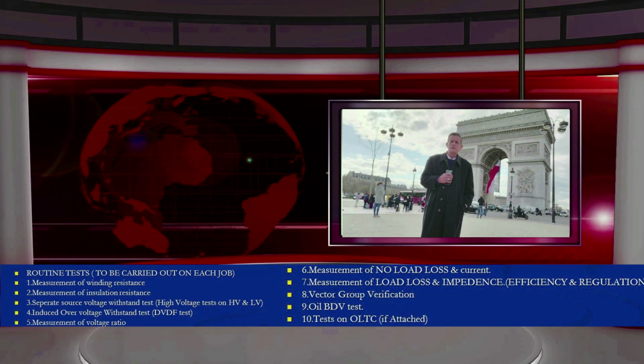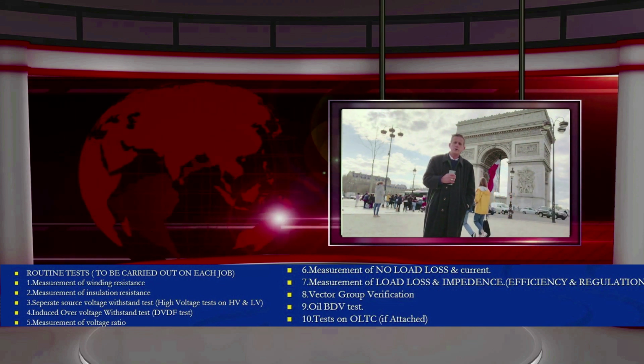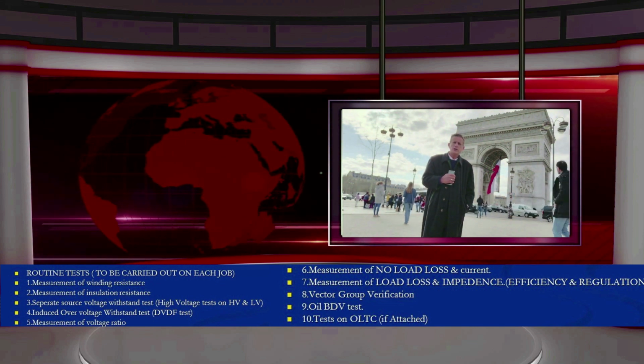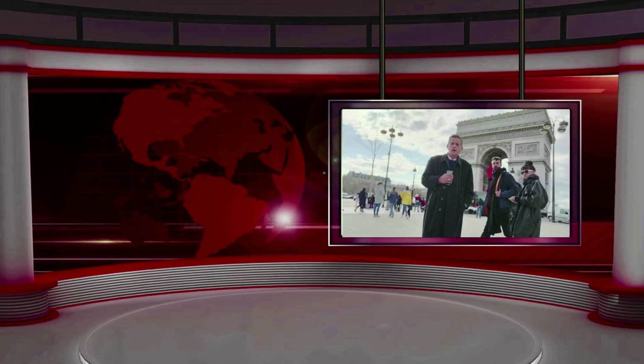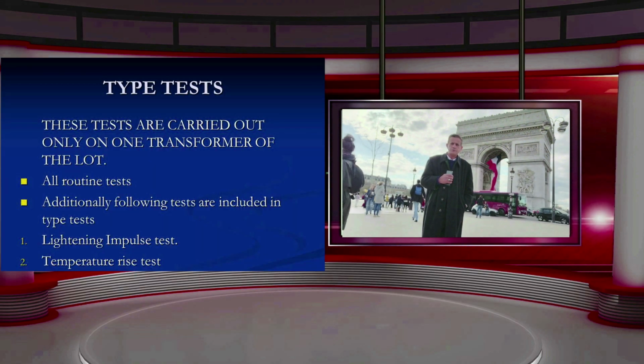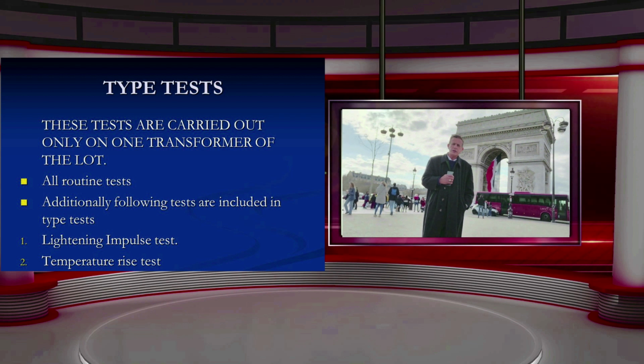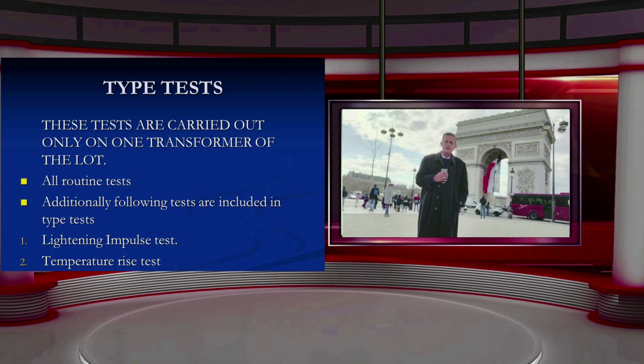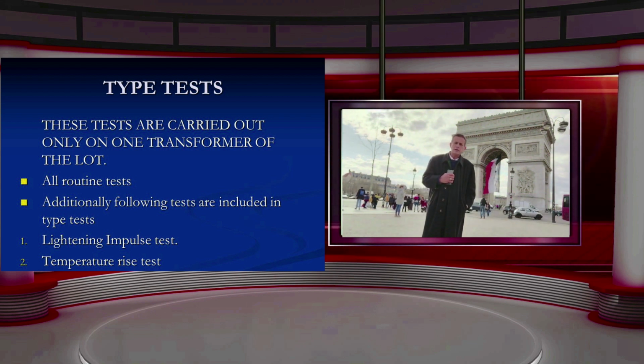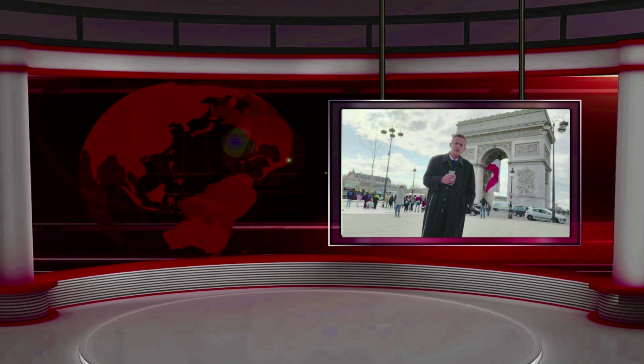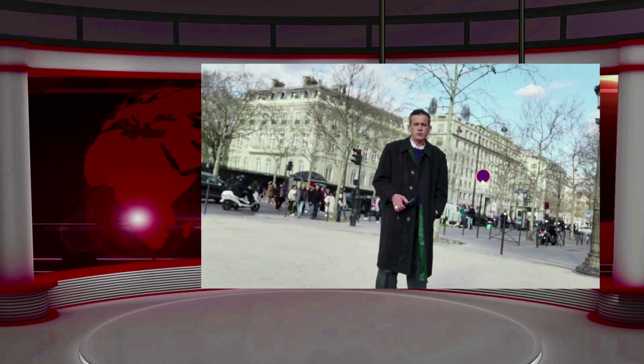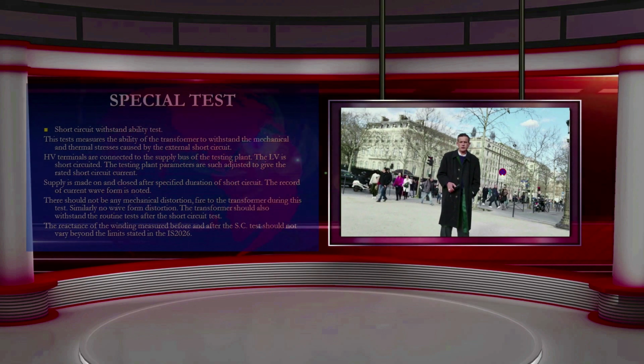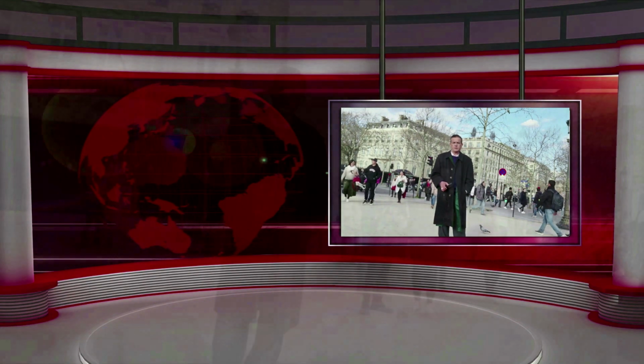We'll start with the routine tests. There are up to 10 tests which are considered routine tests. Routine tests shall be carried out for each single transformer, and then 2 or more tests will be added to this routine test for the type test, which will be carried out for a single unit, a sample unit, to prove the design criteria. And then after type test, we'll be moving to special tests. Special tests are based on the customer requirements. Some customers need some additional tests to be carried out, like noise level test or partial discharge test.